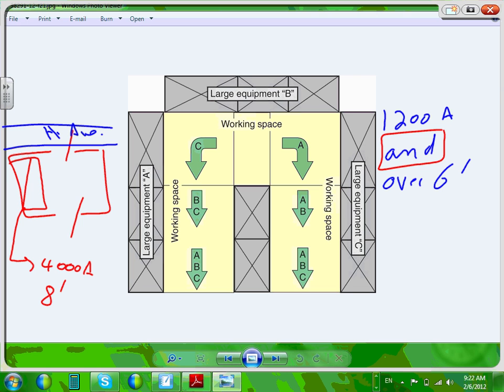Or option number 2, guys: if you can't have the 2 entrances, they give you an option, which is to double the clearances. So take this: if this was a 4,000 amp panel, the length of it is 8 feet, and the voltage is 480/277. Make sense? Large equipment.